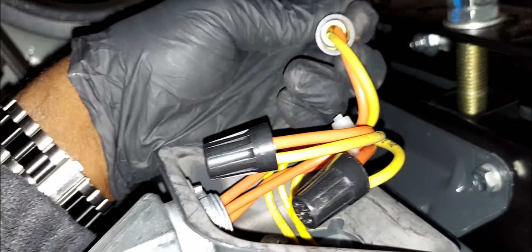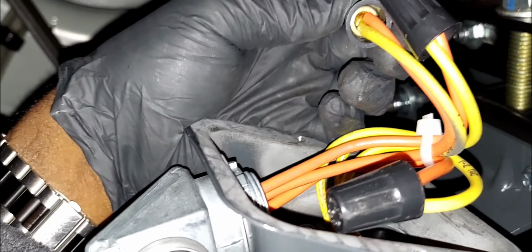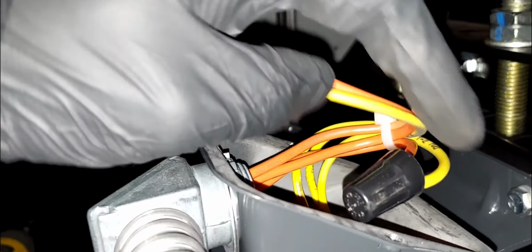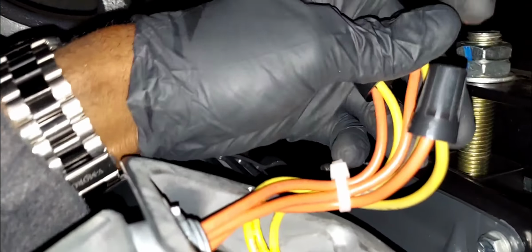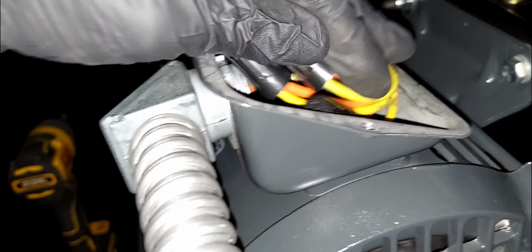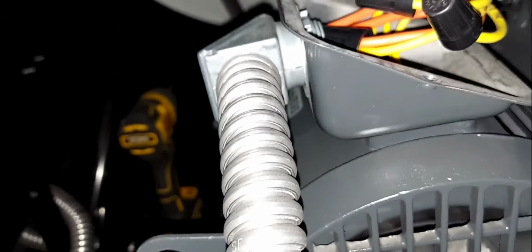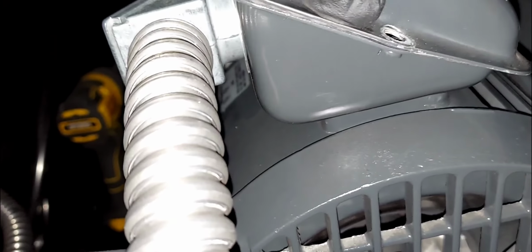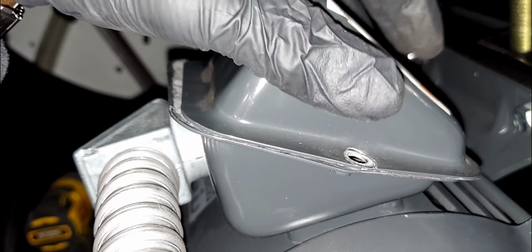All the connections are solid. So I had to open this anyways because, if the overload is tripped outside in the panel, it could have been because you have a loose connection here. So, as a good practice, I'd have to come in here anyways and check this to make sure that my connections are solid, and they are solid. No problems here. Everything is good. So I'm gonna close this back up. I'm gonna go test with my meter to verify that those overload contacts in fact are open, and then reset it and then do some amperage readings.